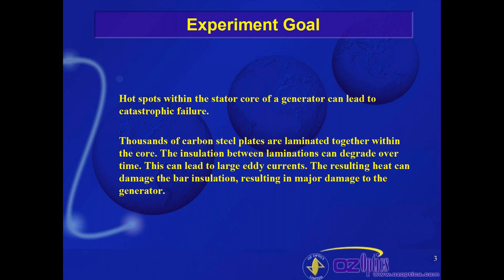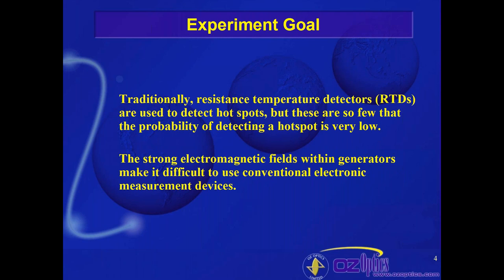The whole purpose of this experiment was really to determine: can we monitor what's going on inside the generator while it's running? Traditionally, devices called RTDs — resistive temperature detectors — have been used for detecting hot spots. But unfortunately, each of these requires a separate wire. If you have dozens or even hundreds of RTDs inside a system, that's an awful lot of wiring. RTDs provide only limited point coverage — they detect temperature at specific points inside the generator. You want a bigger, broader picture: what's going on between these RTDs? RTDs alone just won't answer that question.